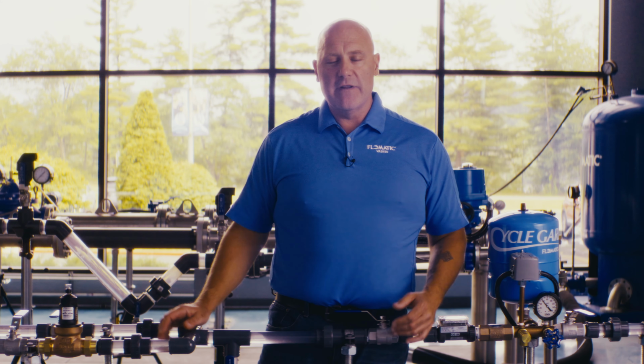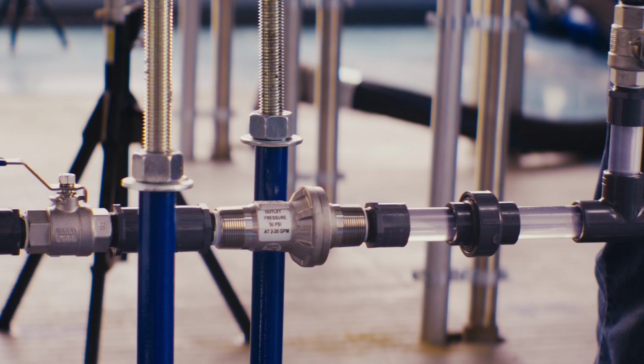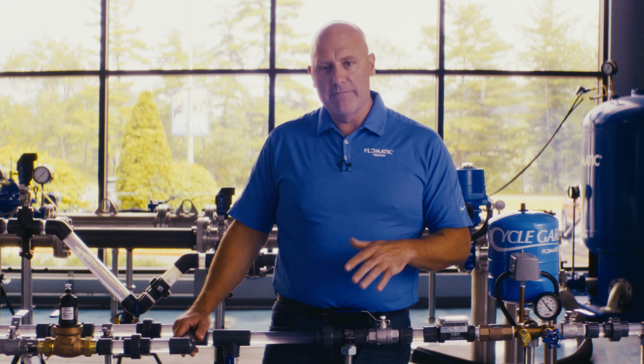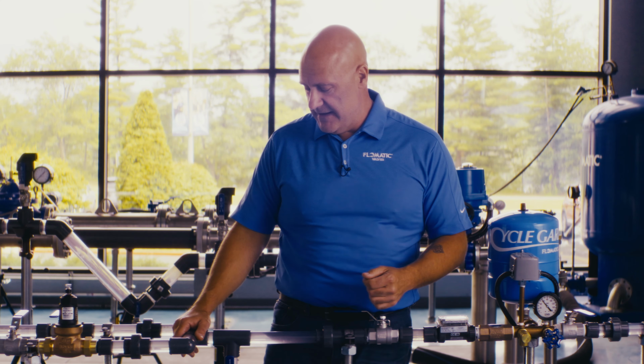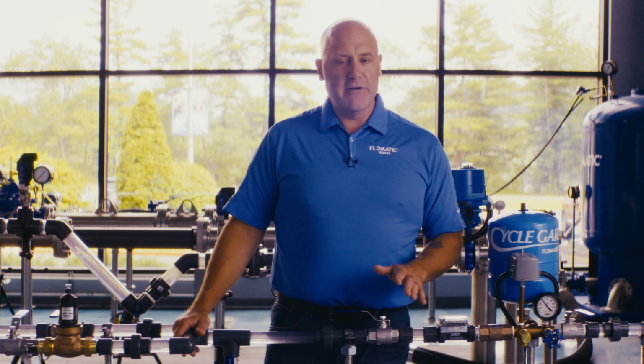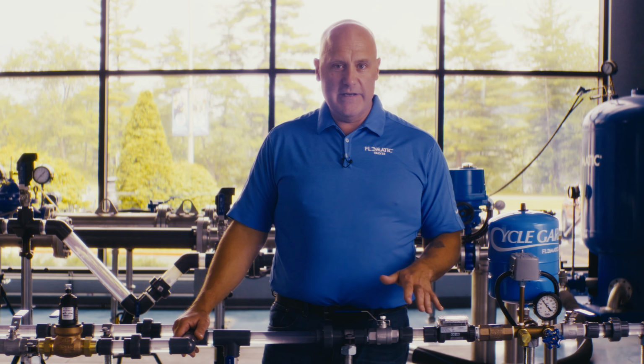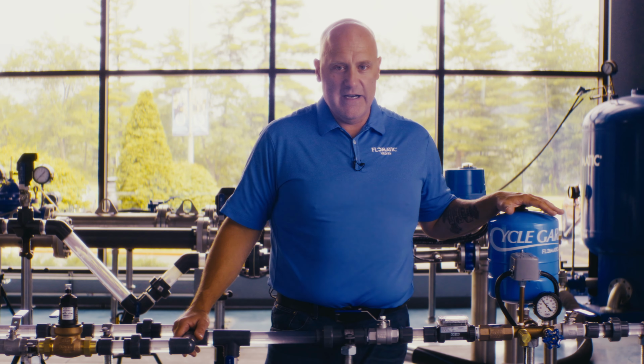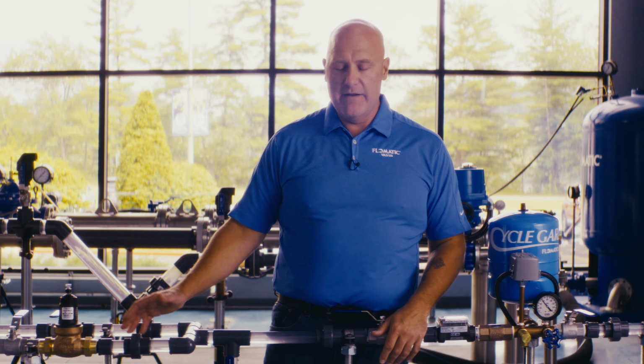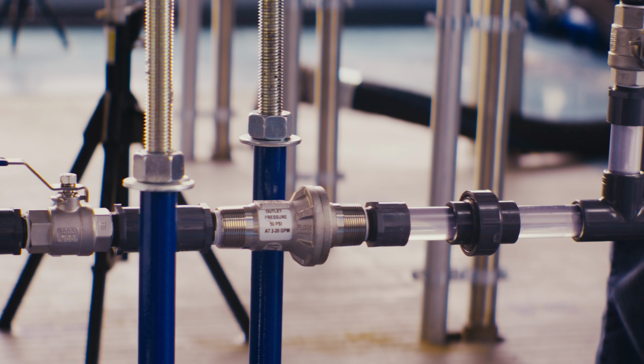These valves are not adjustable, so they must be ordered from the factory at the desired setting. We offer them in 40 PSI, 50 PSI, 60 PSI, and also 70 PSI. The most common one is going to be your 50 PSI. Running in second place is probably 60 PSI. But again, upon initial commissioning, there are a lot of things that need to be considered dependent upon tank size and the pressure of the non-adjustable Cycle Gard.